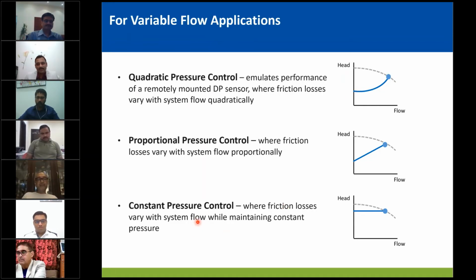Now, the other very rare, but there have been cases where we have seen constant pressure set control curves, but it's also equivalent to the sensor placed in the mechanical plant room. So we have seen it'll be flat or close to flat. So that's the third type of curve.